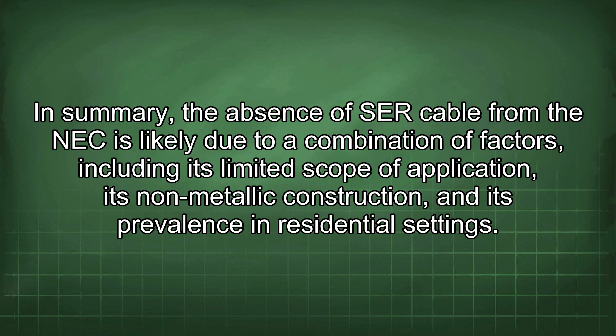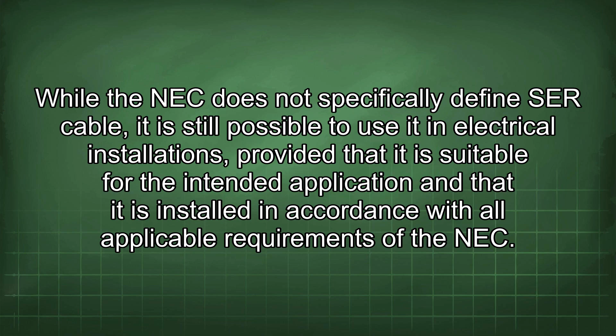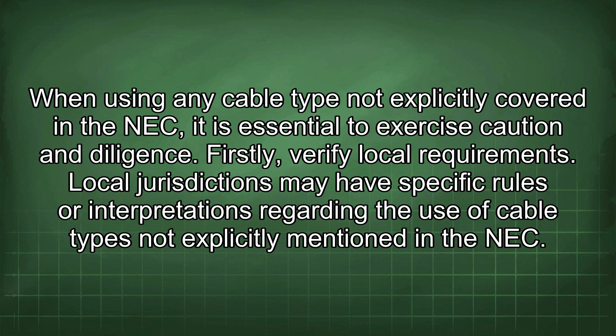While the NEC does not specifically define SER cable, it is still possible to use it in electrical installations, provided that it is suitable for the intended application and that it is installed in accordance with all applicable requirements of the NEC. When using any cable type not explicitly covered in the NEC, it is essential to exercise caution and diligence. Firstly, verify local requirements. Local jurisdictions may have specific rules or interpretations regarding the use of cable types not explicitly mentioned in the NEC. Always consult with the local electrical inspector or building department to ensure compliance with all applicable regulations.